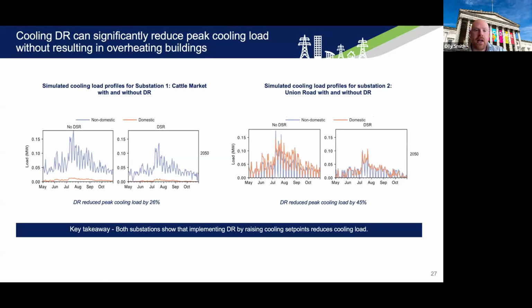So that's for Chorley. And you can see that when we apply demand side response, so that's by changing the set point when there's an increase in the load, we actually reduce the cooling load by 26% without introducing any additional overheating. And it's a similar story for the Rawtenstall substation, where by introducing demand side response, so that is again increasing the cooling set points, we can reduce peak cooling load by 45%. And again, that doesn't introduce any overheating. So demand side response is quite effective at these two areas for bringing down peak demand without causing discomfort. Next slide, please.